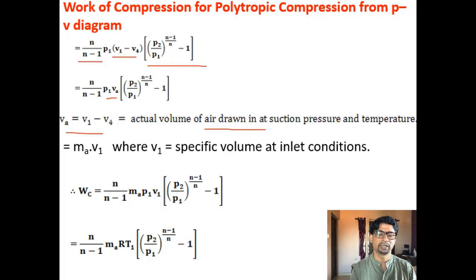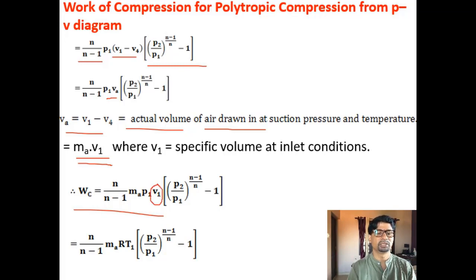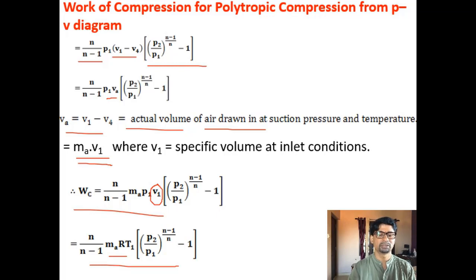So from 3 to 4 the compressed air expands, and from 4 to 1 actual suction begins. V_A can also be written as m_A times small v1 — mass times specific volume. So the work of compression is WC = N/(N−1) times m_A times P1v1 times [(P2/P1)^((N−1)/N) minus 1], where v1 is specific volume at inlet. Since P1v1 equals RT1, an equivalent expression is WC = N/(N−1) times m_A times RT1 times [(P2/P1)^((N−1)/N) minus 1]. If m_A is the mass flow rate in kg/s, this gives the power input to the compressor.